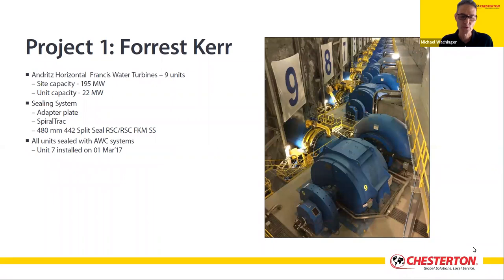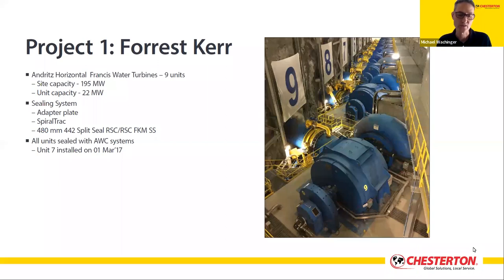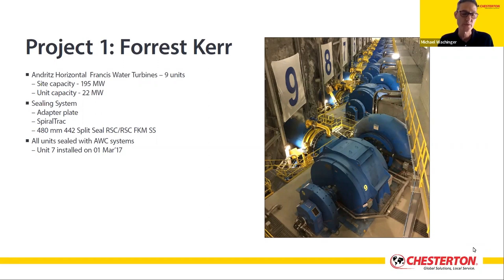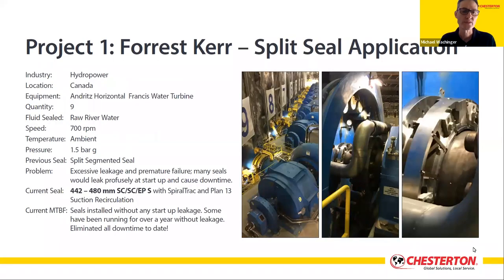The original main shaft seal was a split segmented polymer design which leaked profusely upon startup and, even when controlled, still used huge amounts of flush water. Many times these segments would break, causing unplanned downtime and long hours of sealing rebuilds. In 2017, the first axial split mechanical seal was supplied to unit seven at Forrest Kerr. The clean flush water flow was cut down to an eighth of its original supply initially, and gradually reduced to a trickle as the mechanical seal obtained its lubrication from the river water.